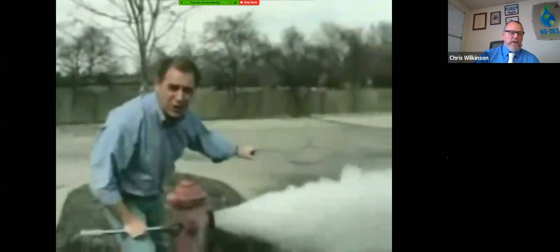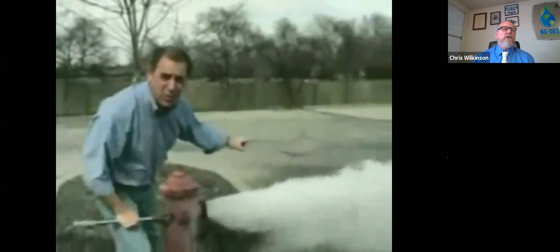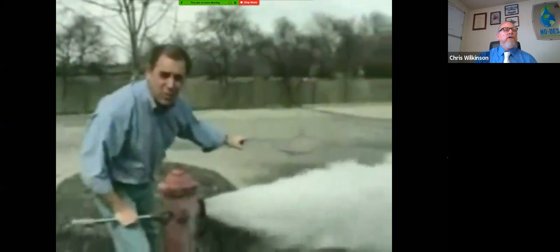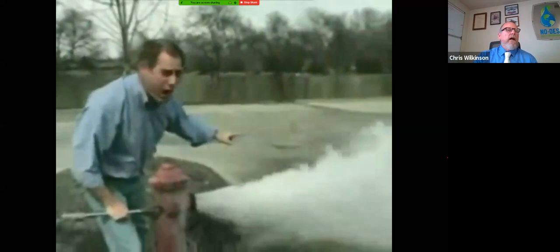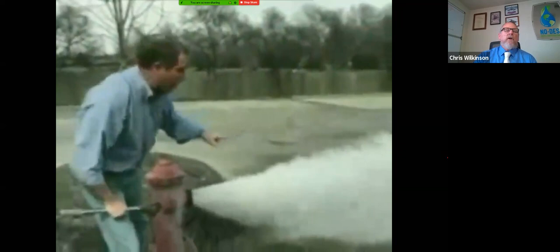I'll talk a little bit about you. The utilities must provide safe drinking water at the lowest possible cost. And as environmental stewards, the message we send our customers must be clear and concise. We'll never have enough water to waste. So what is water distribution system flushing? It's a process that cleans the inside of the water mains by creating high flows. Most utilities flush as often as possible, sometimes 4 months per year or more, achieved by opening fire hydrants, blow-offs, or flushers. We've had some of our customers flush up to 2 weeks at a time, nonstop, 24 hours a day. Anytime, like on the picture in front of you, a 4.5-inch hydrant port is going 22,500 gallons every 15 minutes. That's a lot of water to waste.